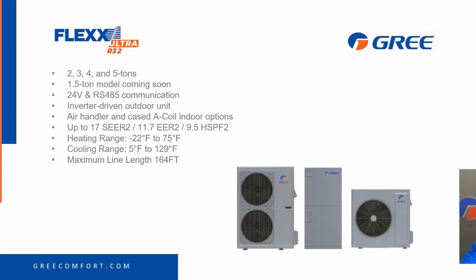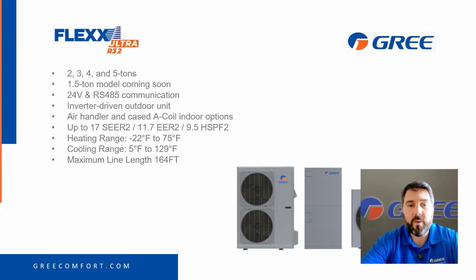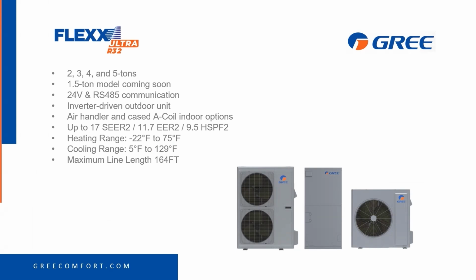So before, if you're familiar with the FLEXX that we had before, it was 24 volt control. And what that was great for was change outs. It was easy to use whatever thermostat you wanted to control the system with. And so it was a unitary replacement option. Now it has RS485 communication in addition to the 24 volt communication.